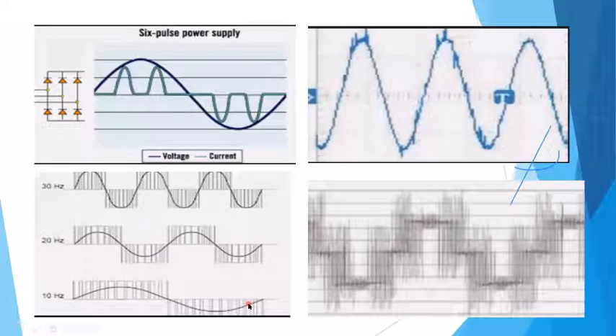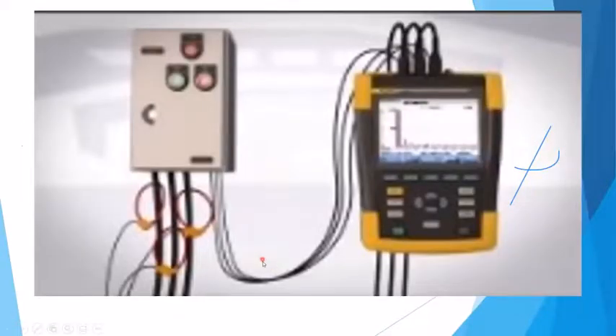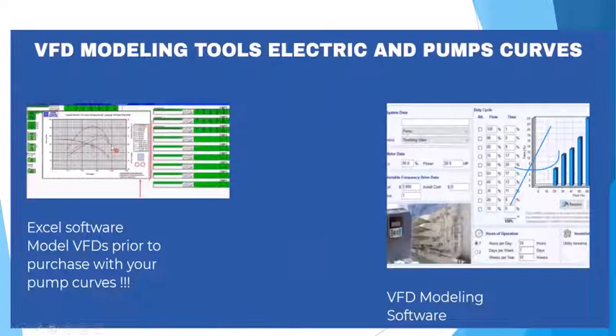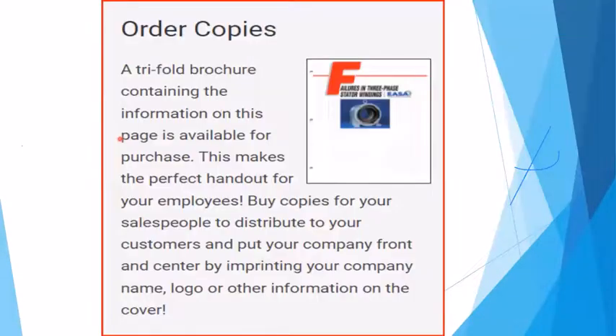when we're slowing this frequency down, we have to be careful about the effect on the speed and characteristic point of where we are on the pump curve. And you can see it drops off quite dramatically, but also when you change the speed, once you put these values in, it also changes the pump curve. So the curve is not the same, because all of a sudden we're running at 55 Hertz, which is maybe 1700 RPM. That curve test point that they had at the factory changed.